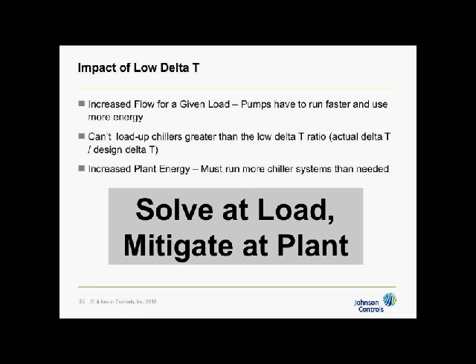The impact, we started to discuss that for a given flow, for a given load, pumps have to run faster and use more energy. So our secondary pumps are literally using more energy, so that draws more energy. I can't load up my chillers, and I have increased plant energy because of having to run more chillers than I need. The only way to solve low delta T is to mitigate it, is at the load.